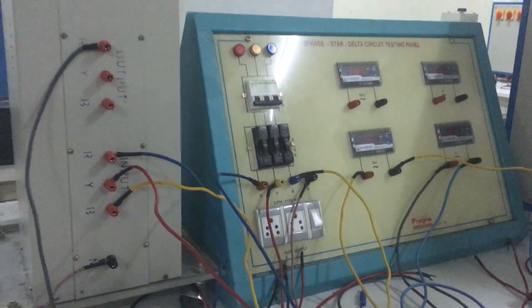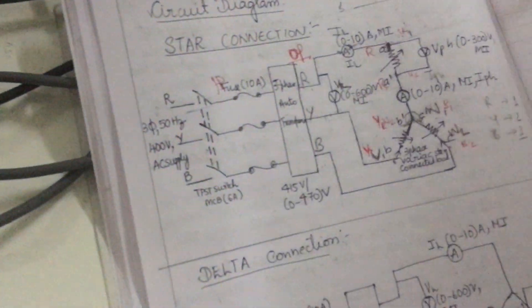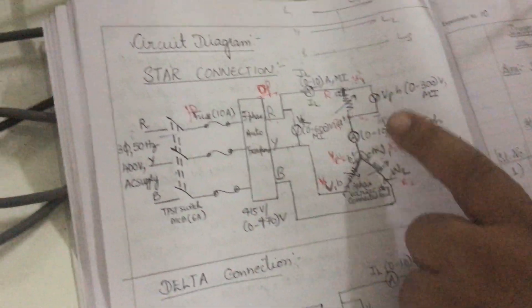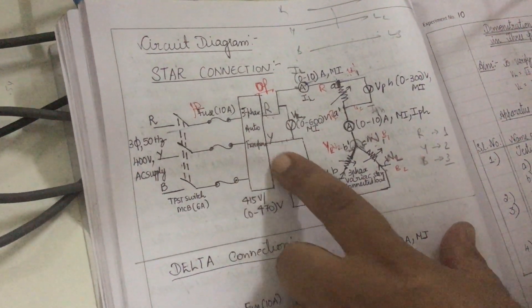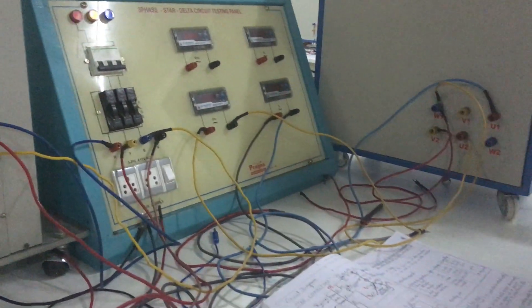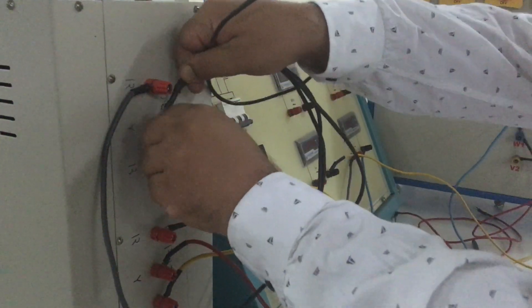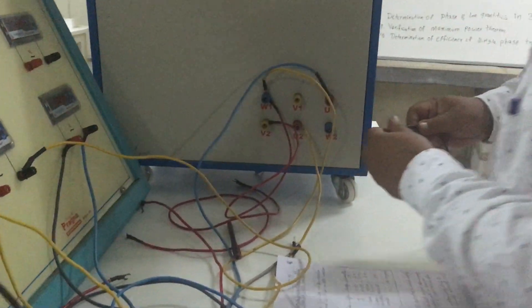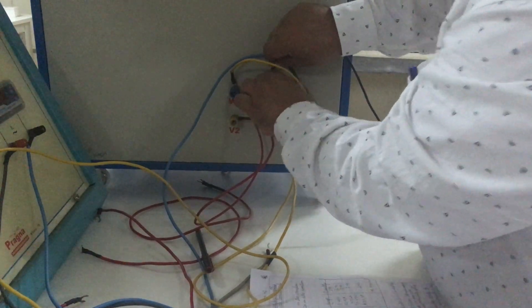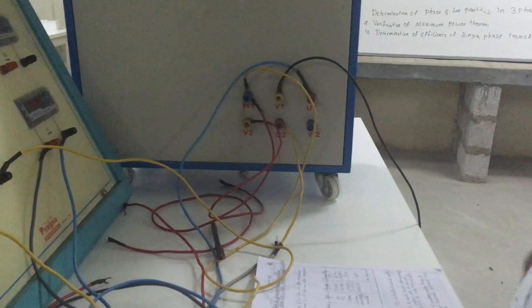The R connection is now complete: R → line ammeter → U1 → phase ammeter → U2 → shorted V2 and W1. Now for Y, take it directly and connect to V1. Similarly, connect B to W2. Once that's done, never give these output connections back to the input side — that is a common mistake.